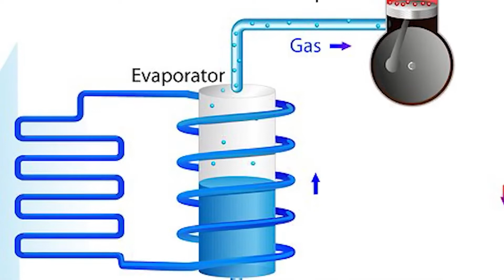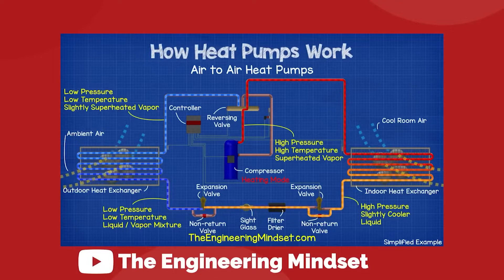Other options exist for heat pumps to conserve energy. Modern heat pumps have variable speed compressors, allowing them to run at the exact speed required to heat or cool your home. A heat pump doesn't need to run its compressor at full power on mild days, so it doesn't — it alters its running speed to only expend the energy it needs.